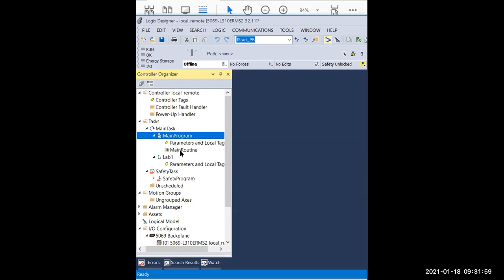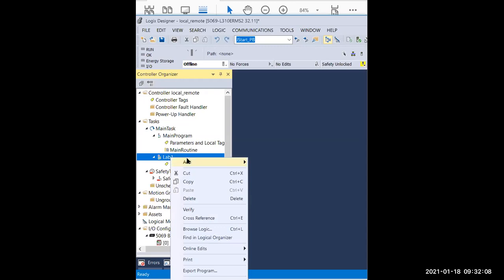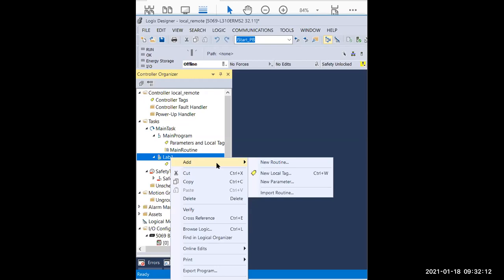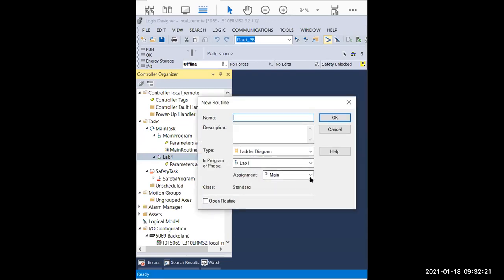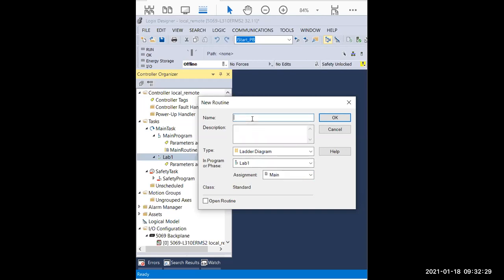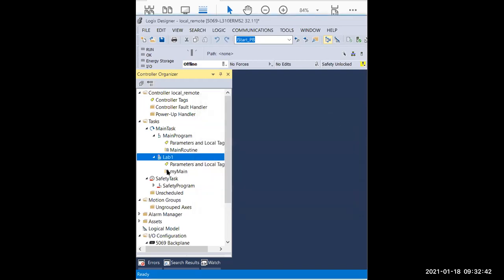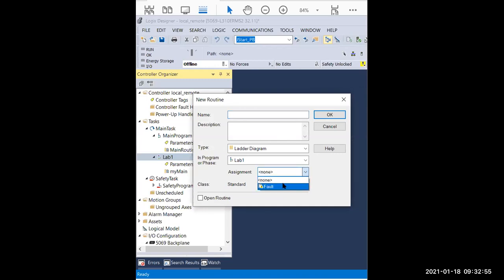Just naming it 'main routine' doesn't count — you have to set that up. For example, with another program, if you right-click, when you add a new routine you have to do it offline. You have a 'Type' choice assignment: you can assign none, just a regular routine, or main routine. You can call it 'my main'. You can see it gets number one on that. If you need to create another routine and add a second one, the assignment can no longer be main routine, because you already had one main routine.